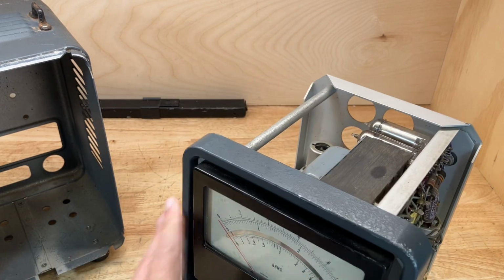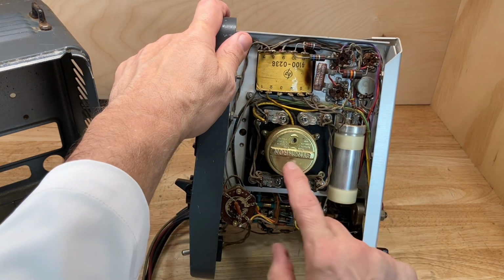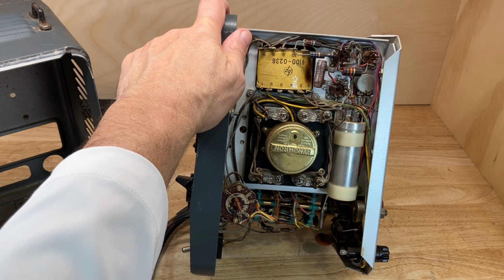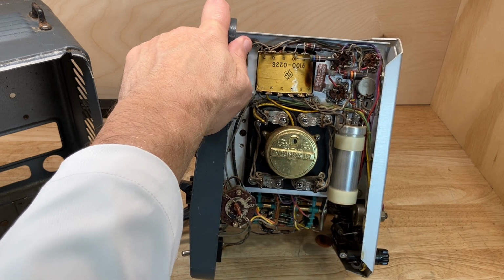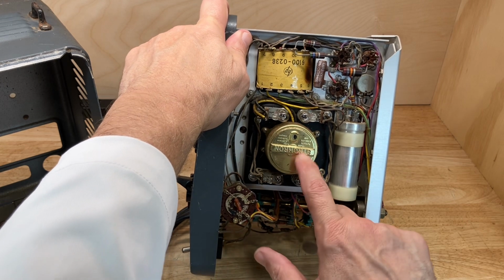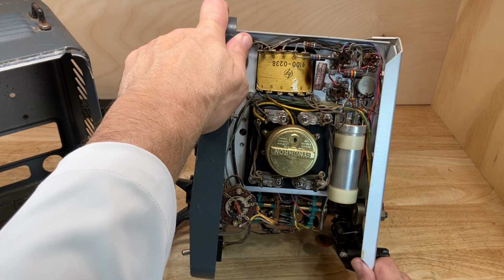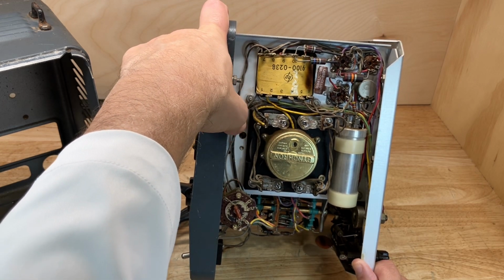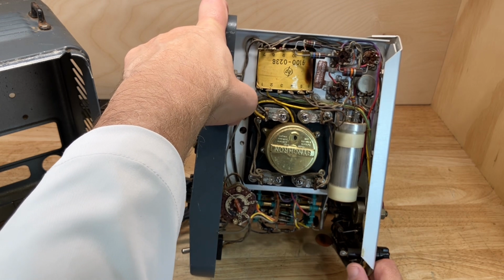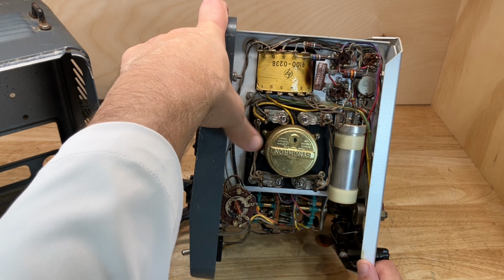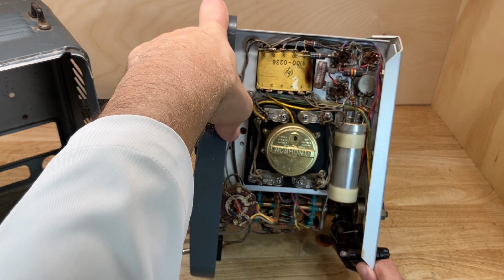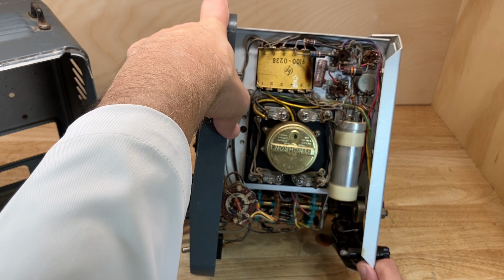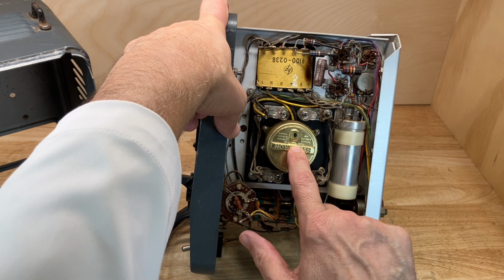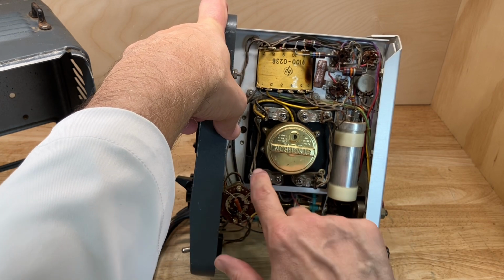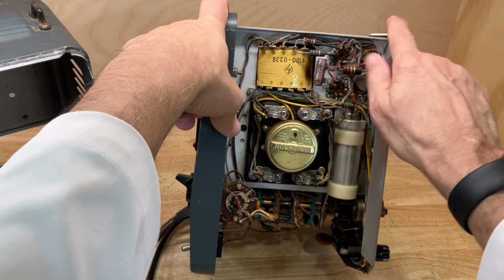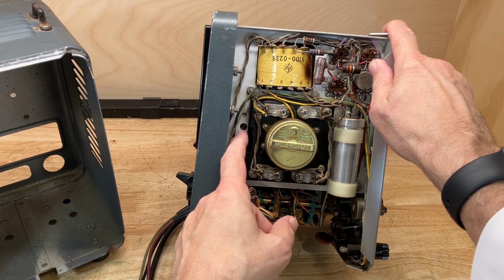One of my favorite things about this voltmeter is that it actually has a motor in it as part of its circuitry. This motor spins when the instrument is on. It's one of the few motorized voltmeters I've ever seen. This motor is part of the chopper assembly that converts the DC voltage into AC voltage, so an AC amplifier can be used to amplify the DC voltage and turn it into an AC waveform, then demodulate that same waveform to turn it back into DC once it's amplified. Later instruments used flashing neon lights instead of a motor with a rotating disc. You can see the little disc on the side over here, and it does freely rotate.